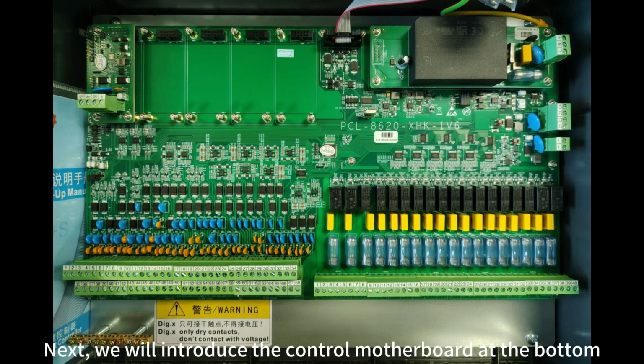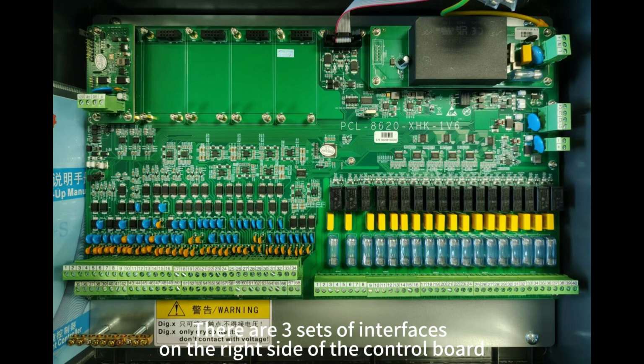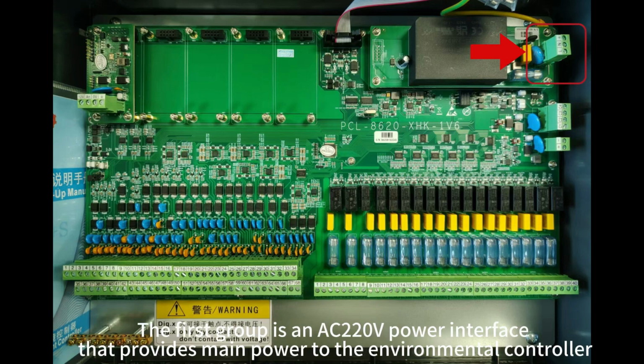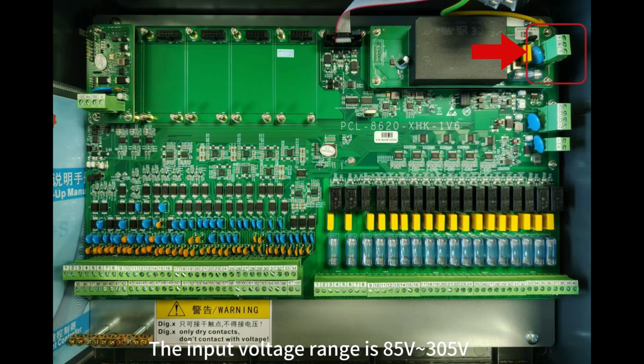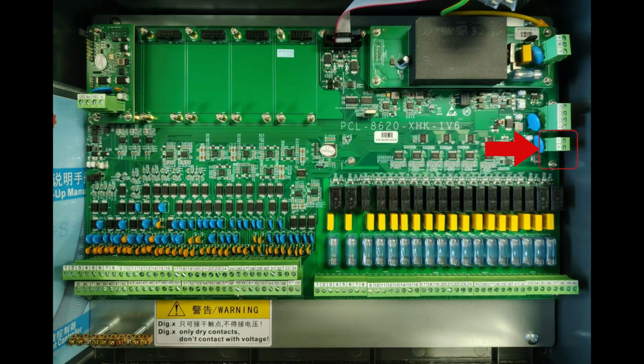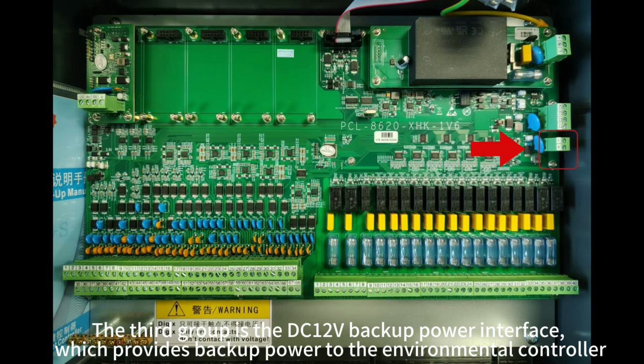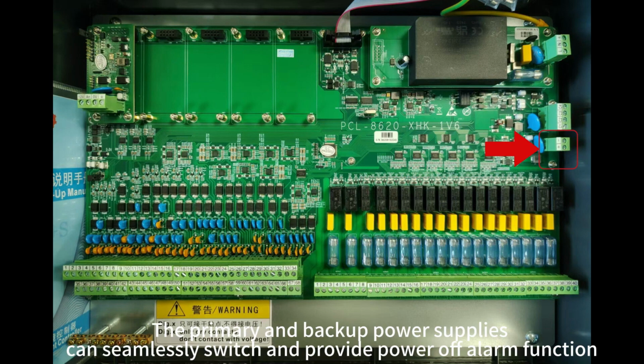Next, we will introduce the control motherboard at the bottom. There are 3 sets of interfaces on the right side of the control board. The first group is an AC220V power interface that provides main power to the environmental controller. The input voltage range is 85 volts to 305V. The third group is the DC 12V backup power interface, which provides backup power to the environmental controller. The primary and backup power supplies can switch seamlessly and provide a power-off alarm function.